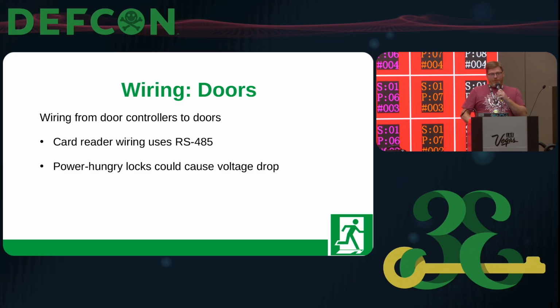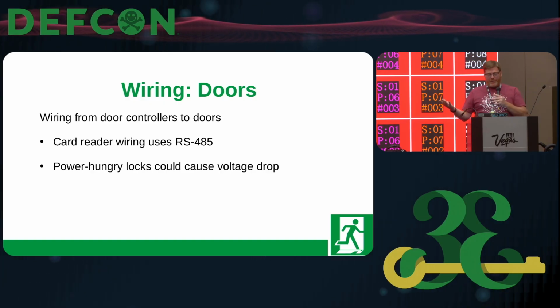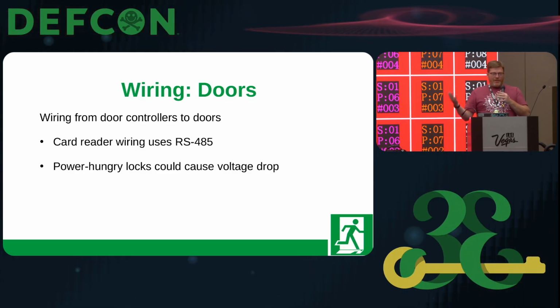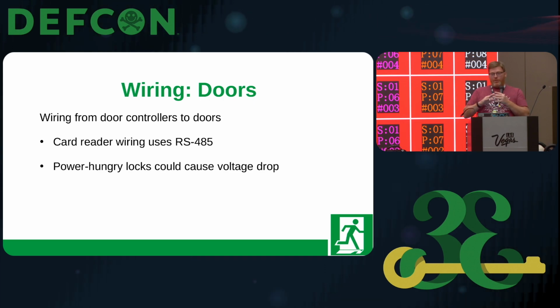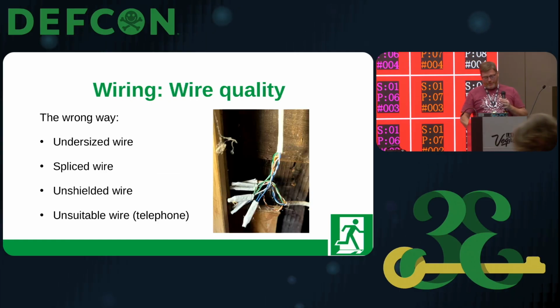Then you have to think about the wiring from that door controller to the actual doors. The card reader wiring also uses RS-485 for newer installations, so there's some consideration there. But also you have kind of power-hungry locks like magnetic locks or crash bars that can use a lot of electricity, and then you're putting a remote power supply out there. So you kind of have to decide where in my building can I minimize all of these issues. And then also wire quality.